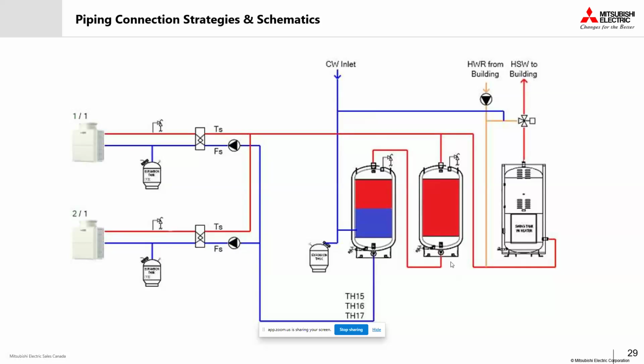Okay, so moving on to plant design and how a plant loop might look for one of these systems. Let's take a quick look and a walkthrough of a typical plant piping schematic for a system using these CO2 heat pump water heaters. You'll see a couple of modular monoblock heat pumps piped in parallel, each equipped with its own internal pump. Heat is transferred to the building's domestic water loop via a double wall glycol to water plate heat exchanger, which provides that code compliant separation between our glycol mixture and the water.